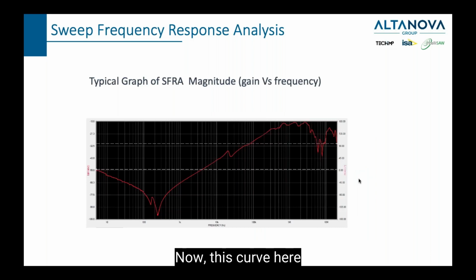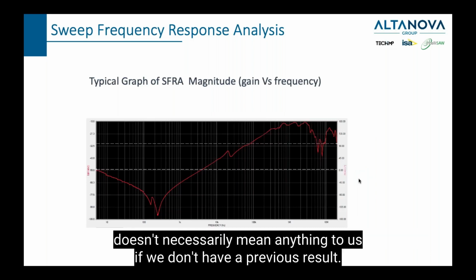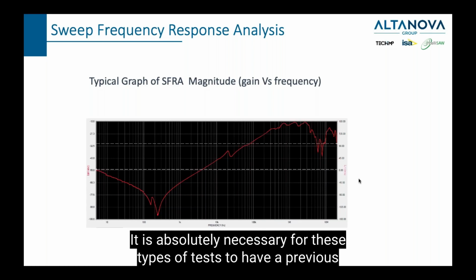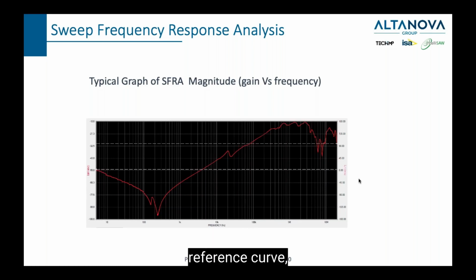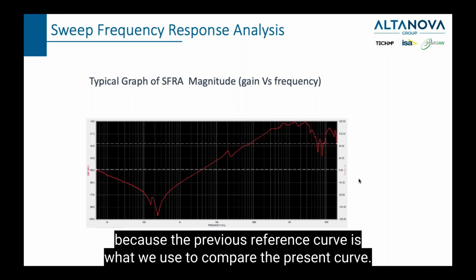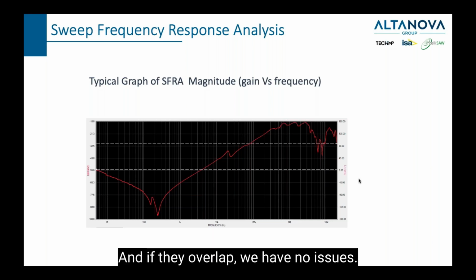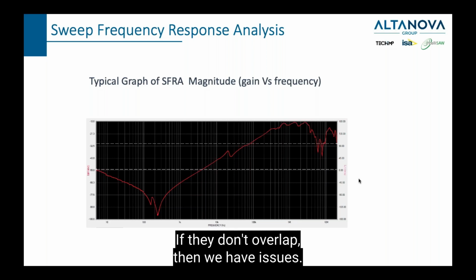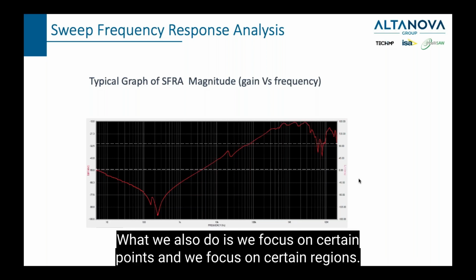Now, this curve doesn't necessarily mean anything to us if we don't have a previous result. It is absolutely necessary for these types of tests to have a previous reference curve, because the previous reference curve is what we use to compare the present curve, and if they overlap, we have no issues. If they don't overlap, then we have issues. What we also do is we focus on certain points and certain regions.